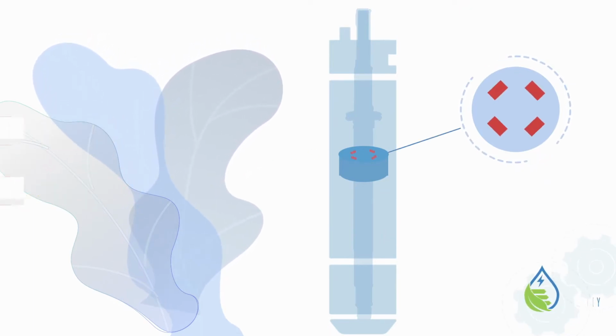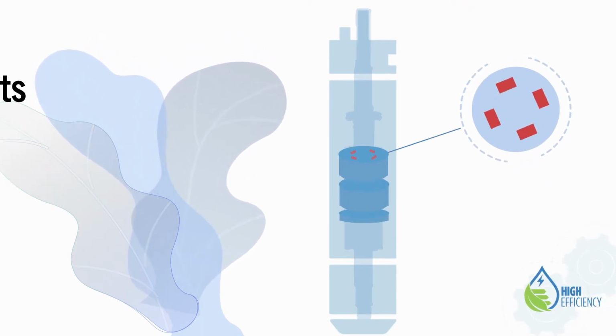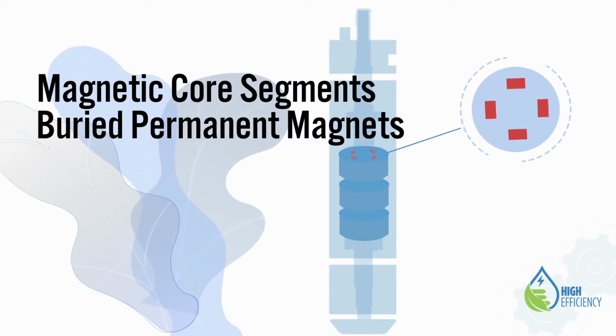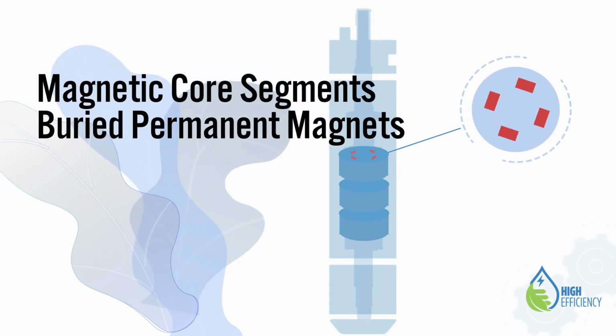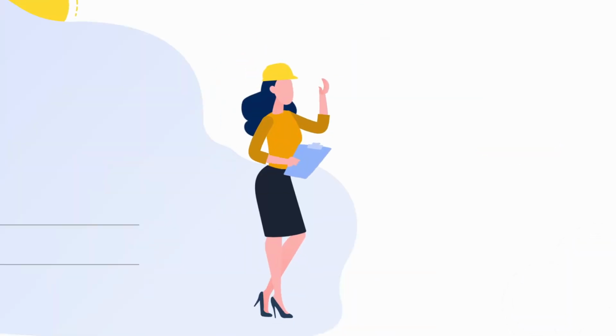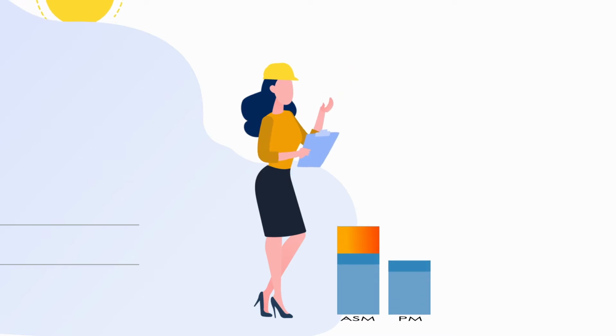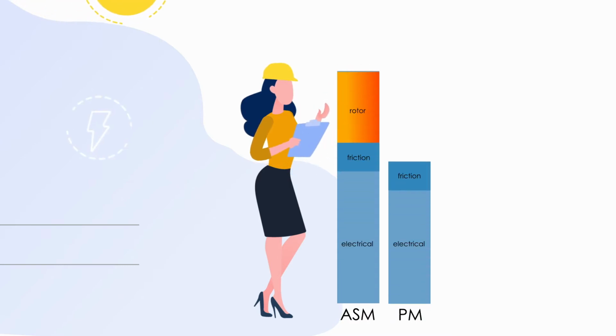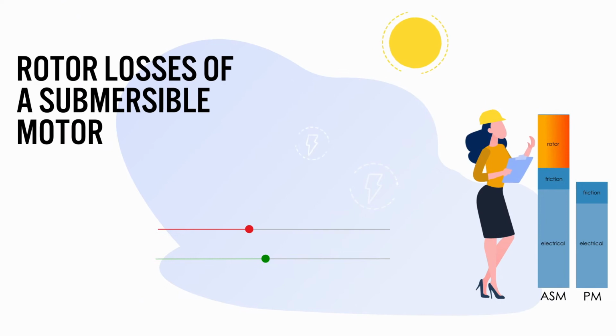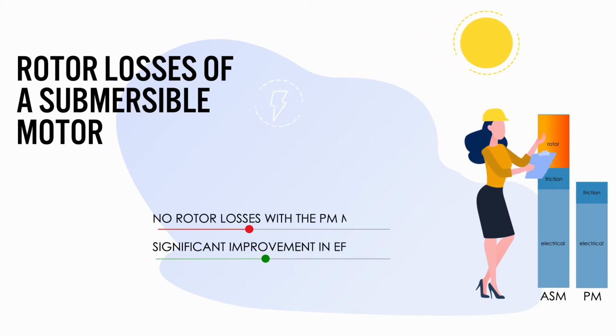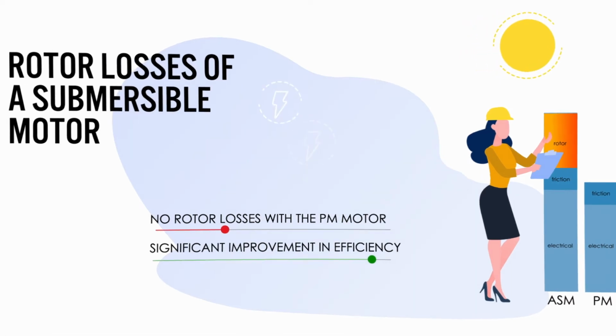The key factor for the high efficiency is the permanent magnet motor. Instead of a short-circuit induction-type rotor, Franklin Electric uses a permanent magnet rotor design with buried magnets and magnetic core segments. The total rotor losses of a PM motor are eliminated, resulting in a significant improvement in efficiency. In addition, the PM motor has less temperature heat rise and requires lower amps to run at the same pump load.